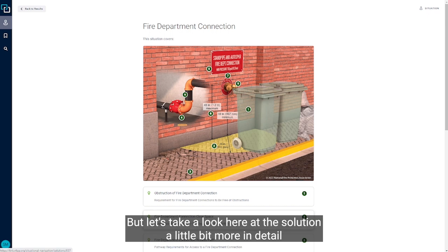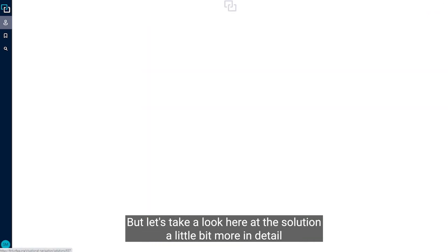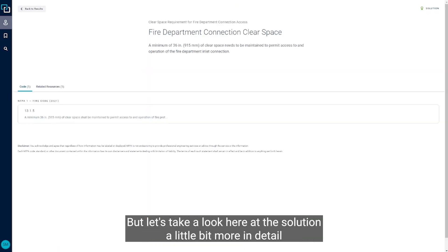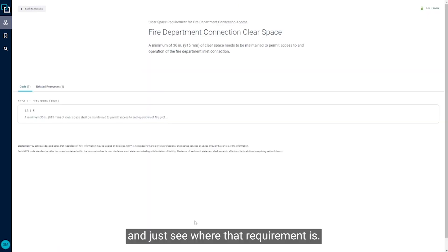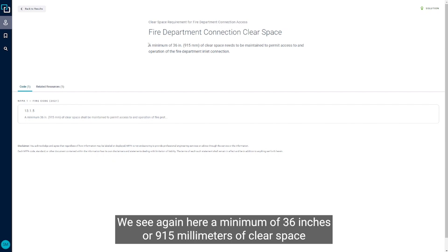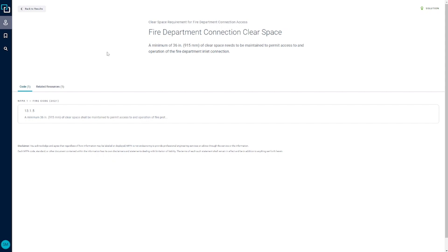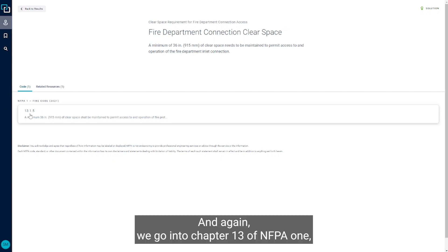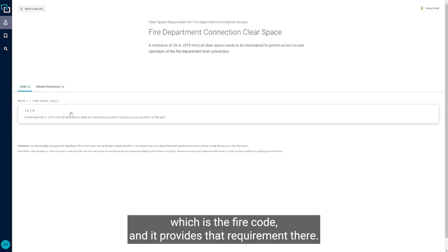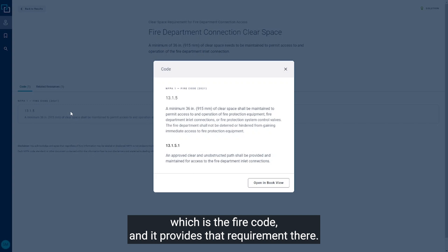Let's take a look here at the solution a little bit more in detail and see where that requirement is. We see again here a minimum of 36 inches or 915 millimeters of clear space needs to be maintained to permit access and operation of that inlet connection. And again, we go into chapter 13 of NFPA 1, which is the fire code, and it provides that requirement there.